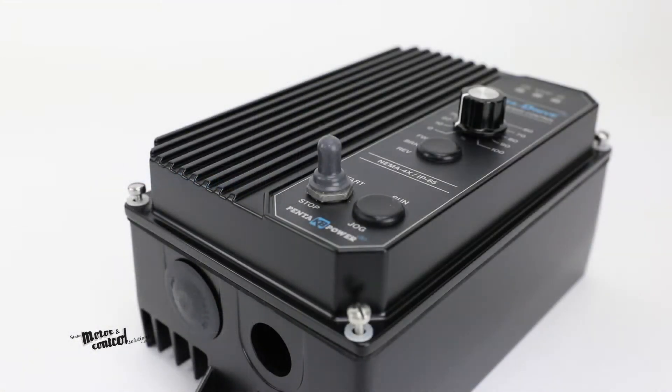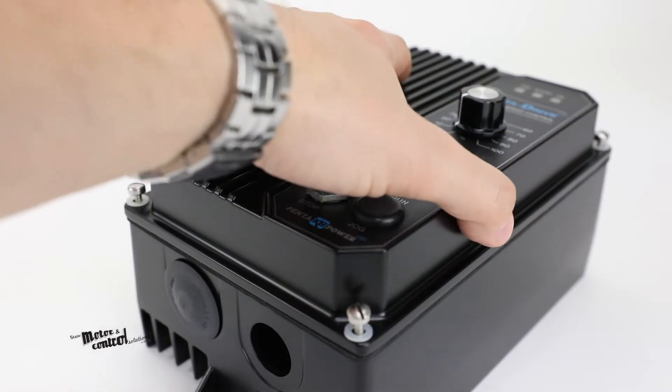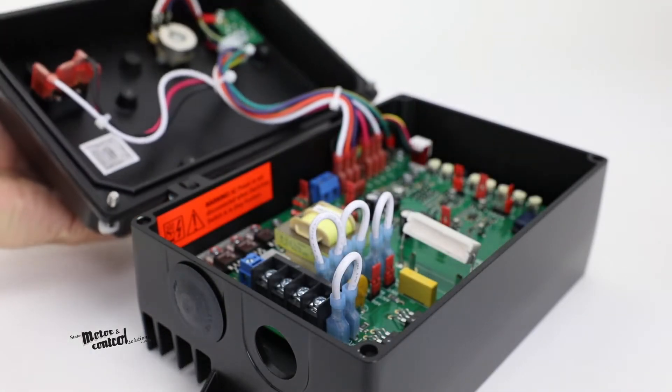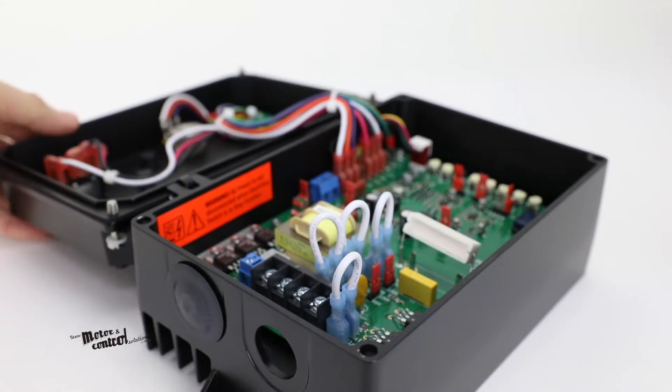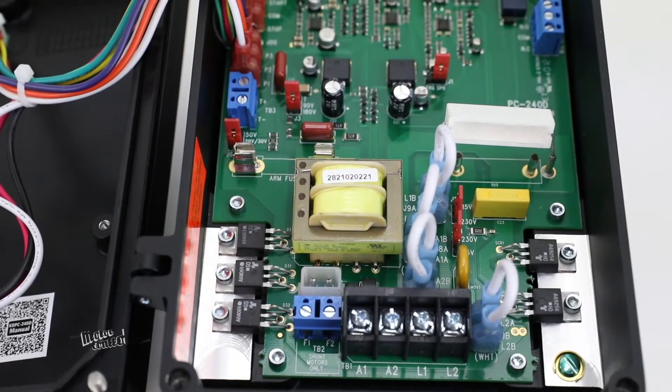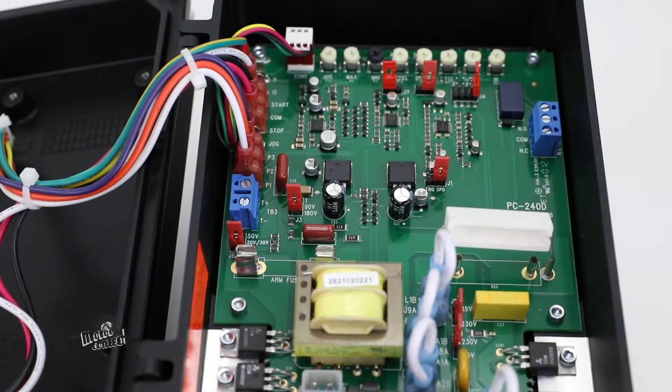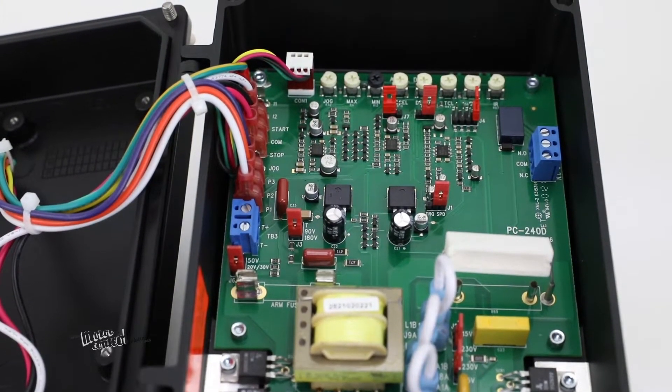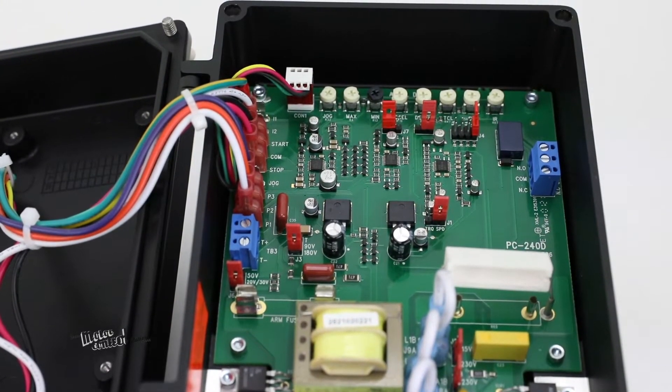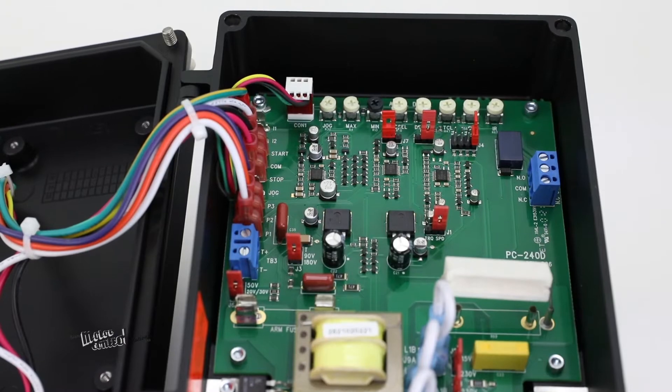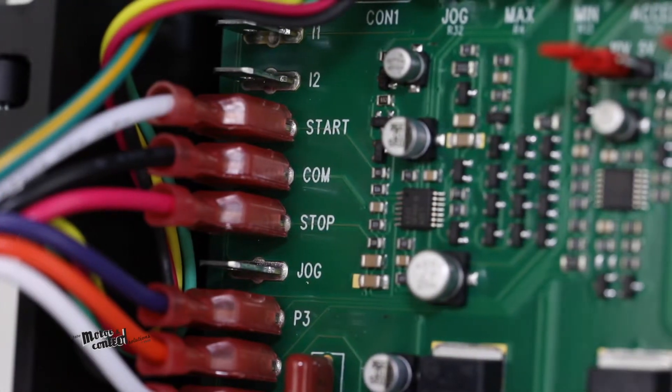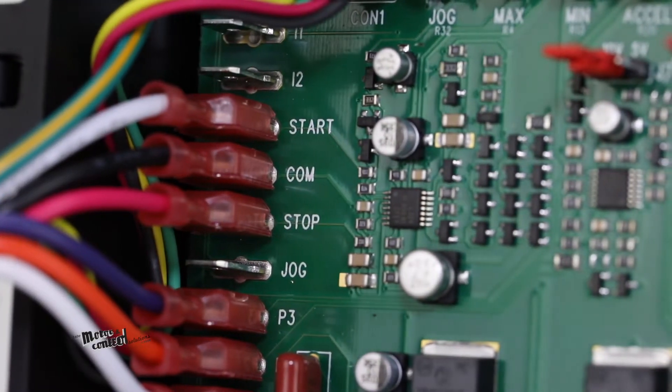Control can be operated through a jumper selection for both the speed and torque modes. Current range is also operated through jumper selection which helps eliminate the need to calibrate IR compensation and current limit for most applications.